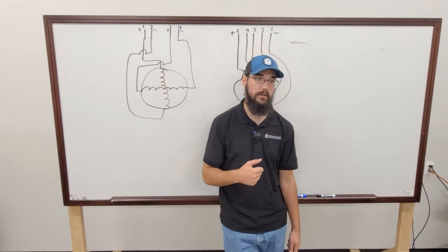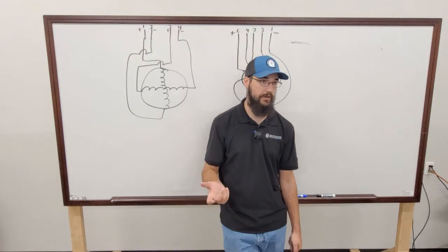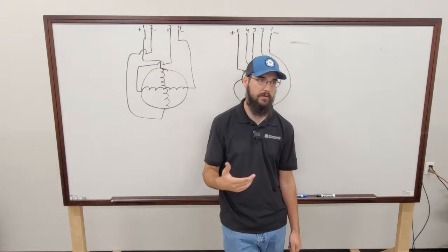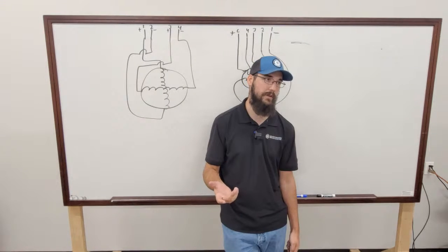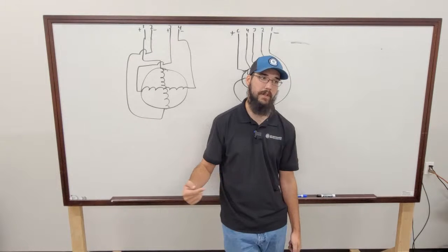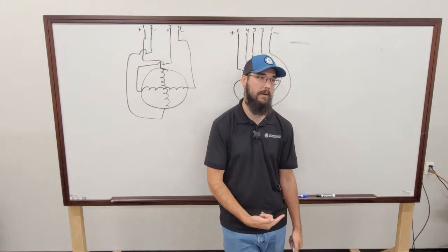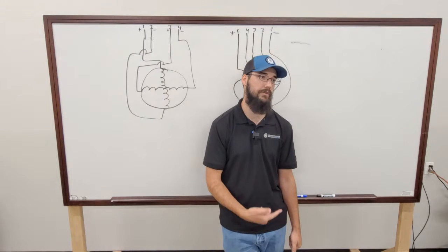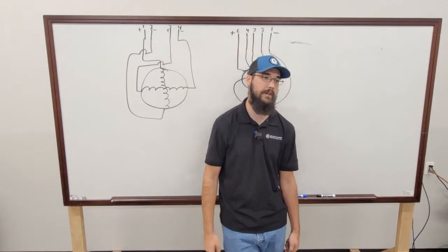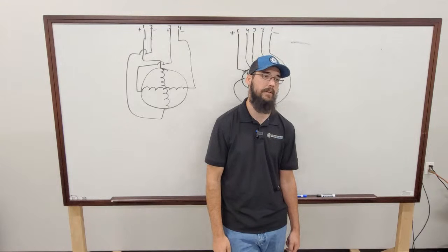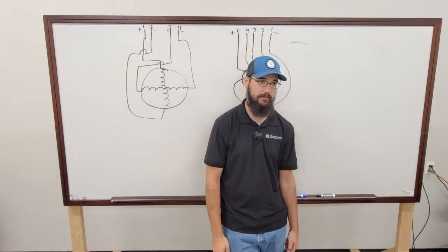RTAAs do this. CVH series Tranes do this. Now, some of the newer ones have high side transducers, but even still the new ones, they're using a thermistor in the bottom of the evaporator on those centrifugals, and the low side pressure you're seeing is that thermistor reading converted via PT inside the logic of the system. So don't walk up to that trying to find where the suction transducer is. You'll never find it. It doesn't exist. Okay? Be careful.